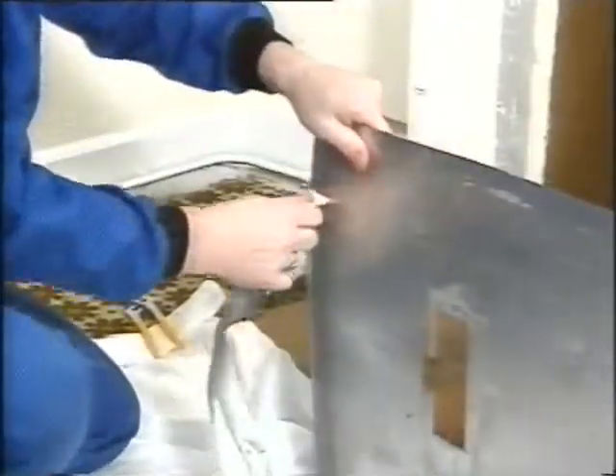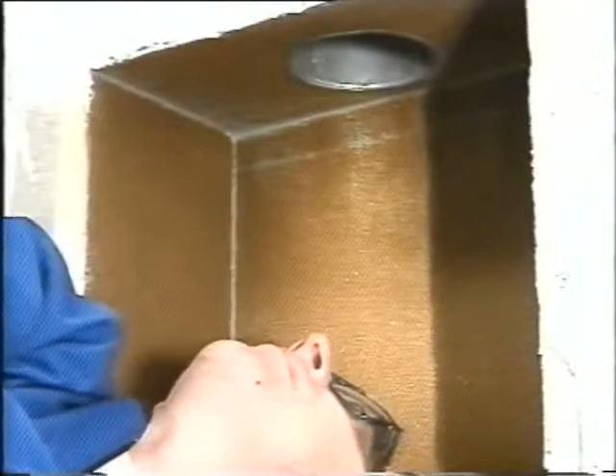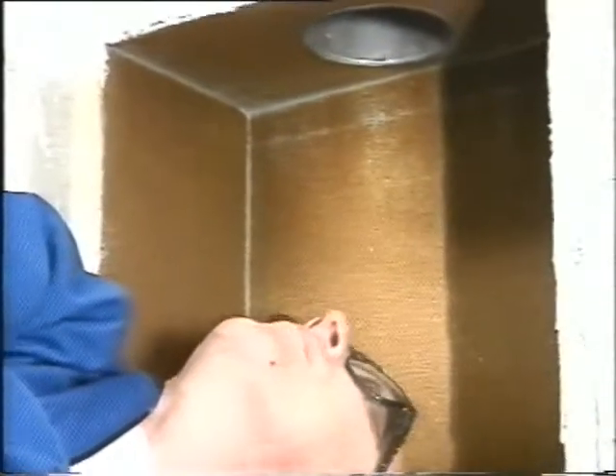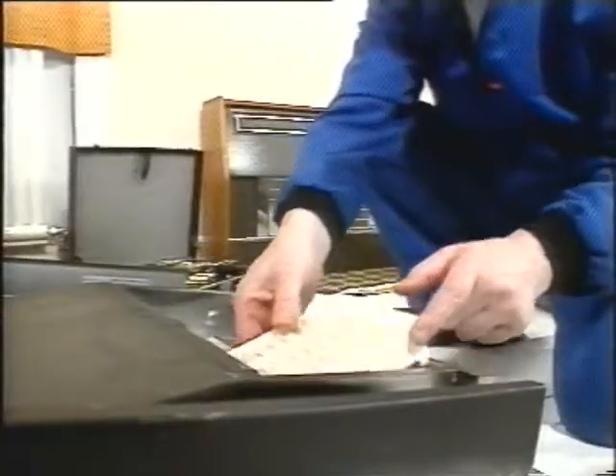When you take the closure plate away, remove all the old sealant and any debris from the recess and check the condition of the chimney. Then, when you're ready, refit the plate and seal it with new material. Then check the flue pull.